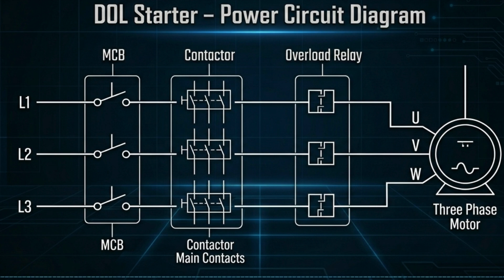At this point, the electrical energy is converted into mechanical energy, and the motor starts rotating to drive the connected machine or equipment. So in simple terms, the power circuit of a DOL starter shows how electrical power flows from the supply source through protection devices and switching components before reaching the motor. In the next step, we will understand the control circuit of the DOL starter, which is responsible for operating the contactor and controlling how the motor starts and stops.